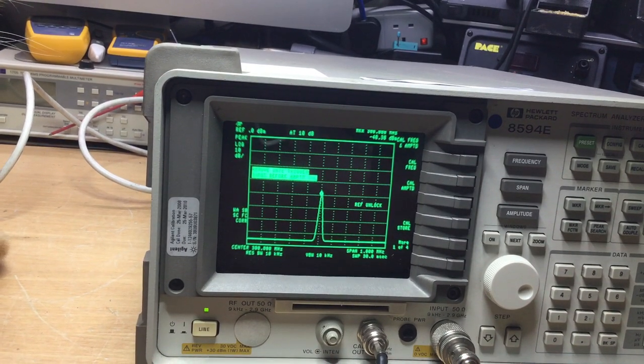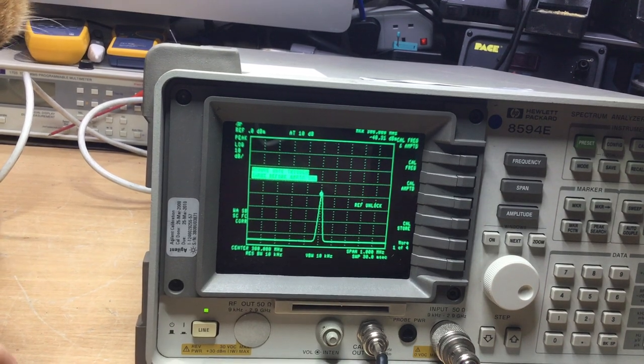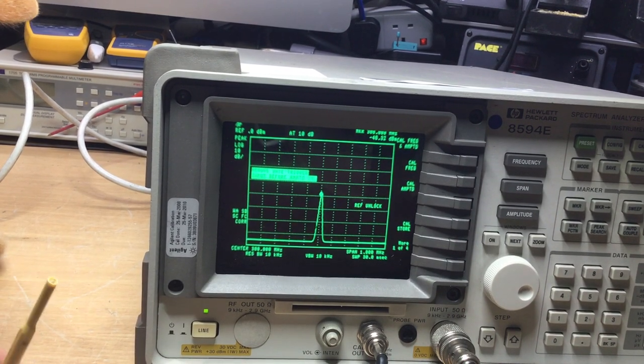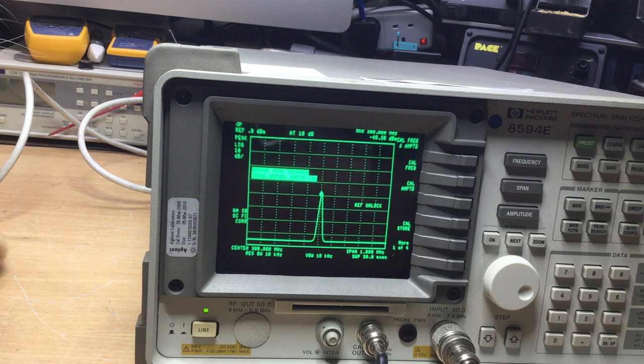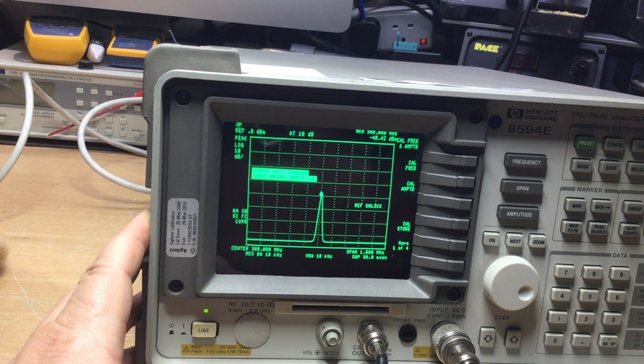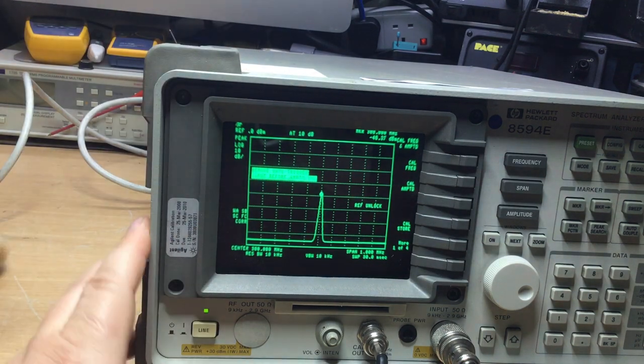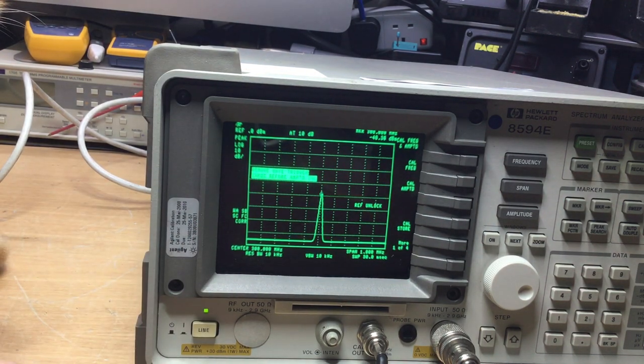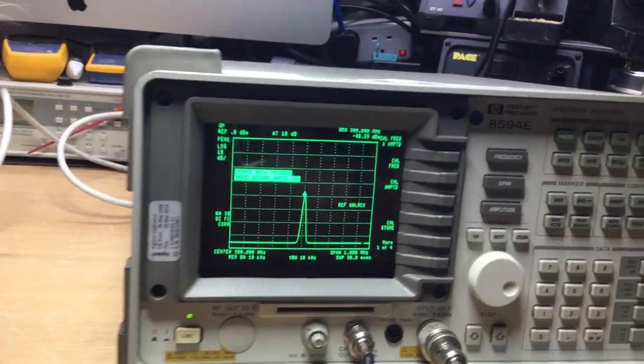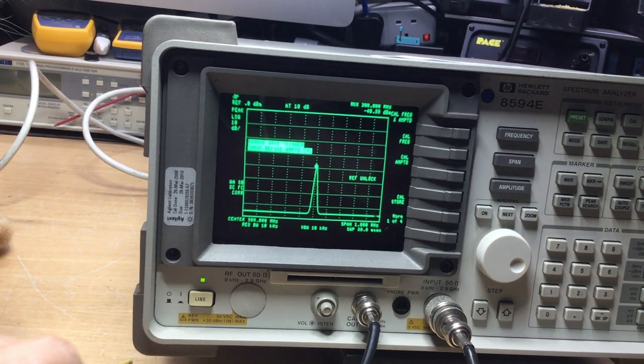right, well, we'll carry on now with the, there's a coarse adjust as well, a coarse focus adjust. It says turn the analyzer line switch off, remove instrument cover, refer to the removal procedure in chapter 3, turn the focus adjustment locator, adjust the coarse. All right, so that's a fine. There's a coarse adjustment inside anyway once we whip the lid off. Another one on the monitor module, so we might be able to sort that out. And the technical manager is looking into it right now as we speak to find out exactly where that is, so no doubt we'll get some more advice.